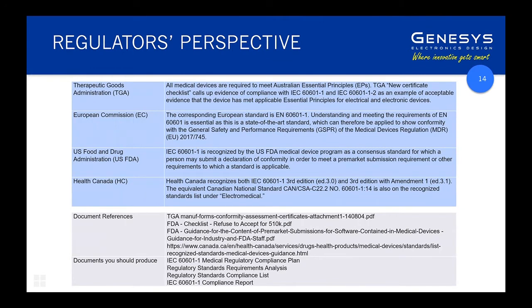You'll find similar answers if you delve into regulatory requirements of other domains, including Japan and China. Globally harmonized standards are very closely aligned with 60601-1 — not completely, due to differences like mains voltage, frequency, and multilingual requirements for documentation. But the core requirements are essentially the same. It's a pretty safe bet that for any jurisdiction, the equivalent of 60601-1 will be called up as a national standard referring to the globally harmonized IEC standard in some form.